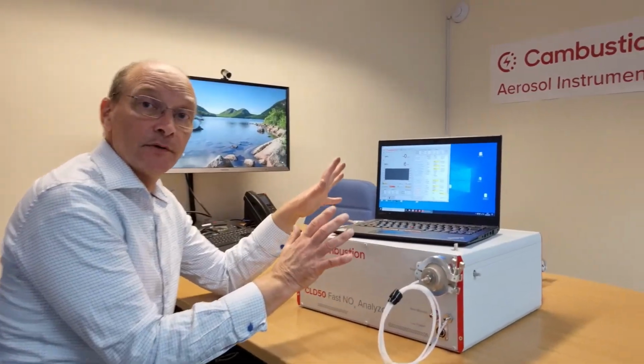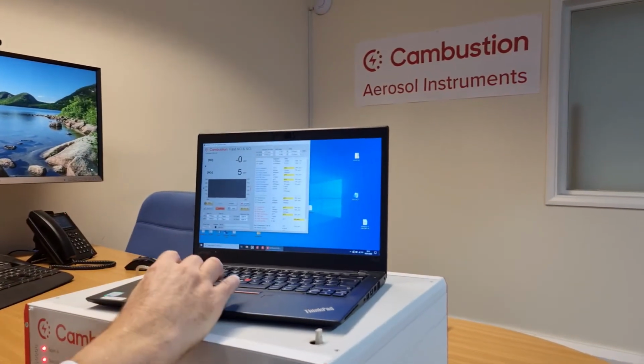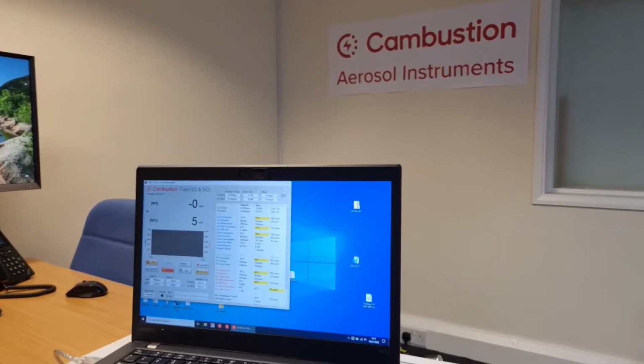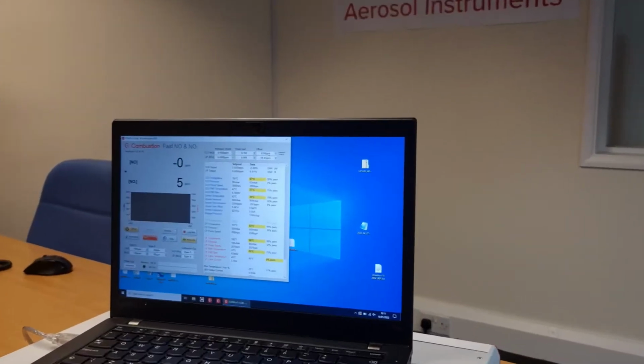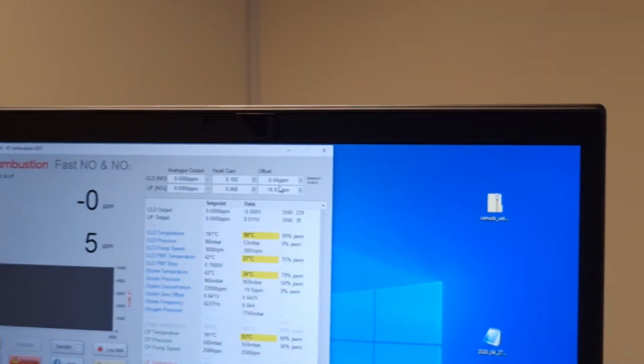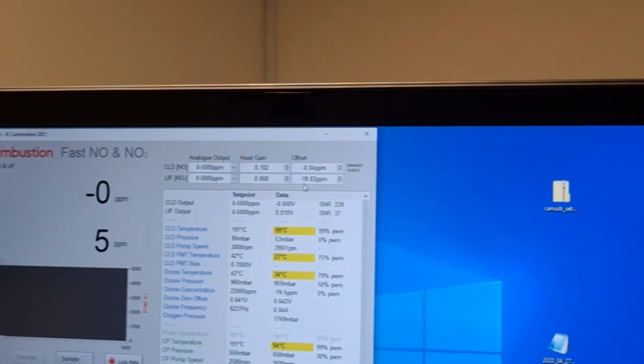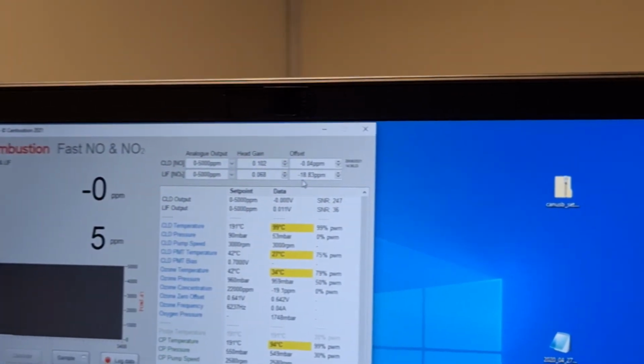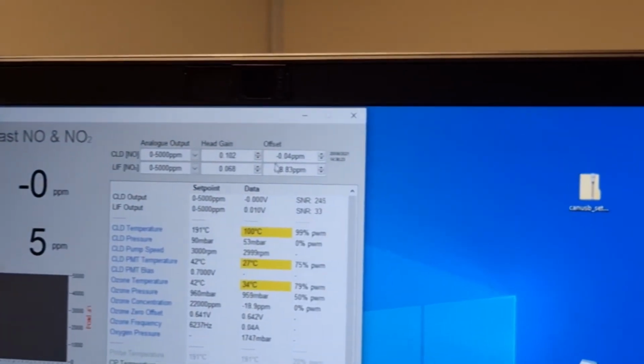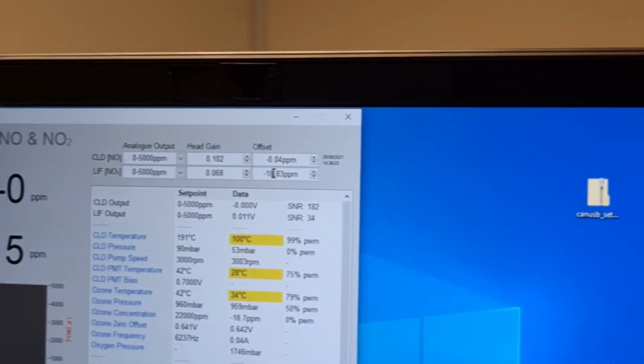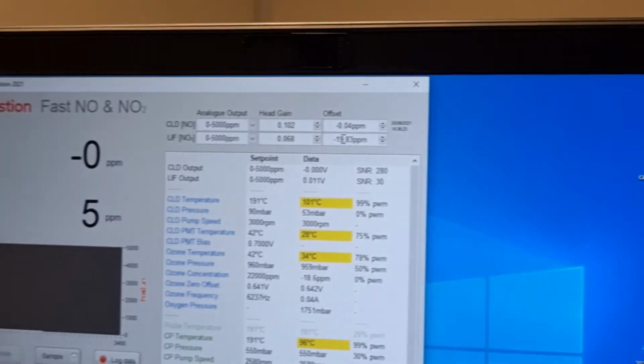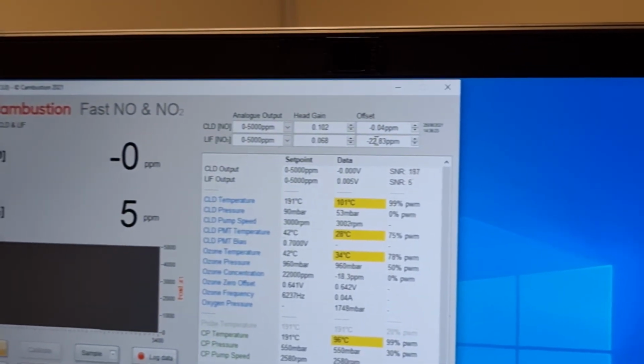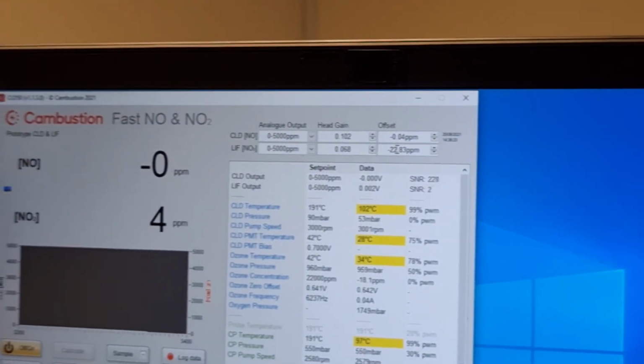While this is warming up, I'll show you some of the features in the software. For example, at the top of our More Info page, we've got the gain and the offset for the CLD and the LIF. So you can see here that we've got a positive offset of about 5 ppm on the NO2. If I adjust this offset down, that will come down and take that offset away.